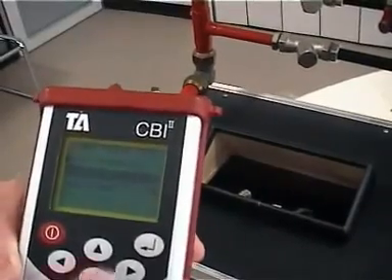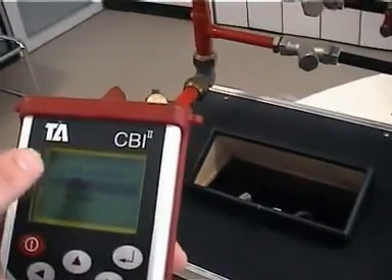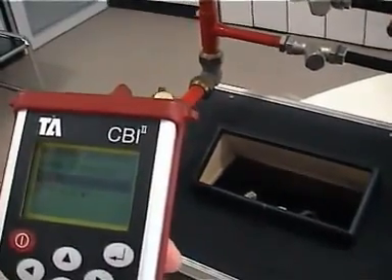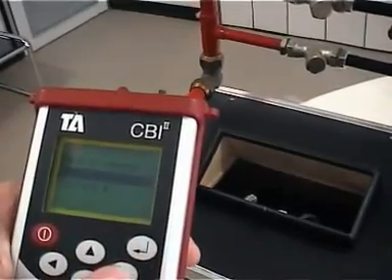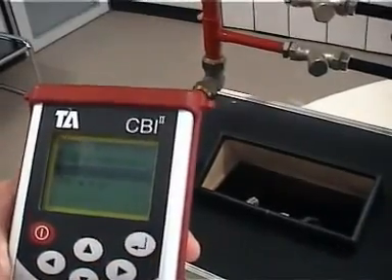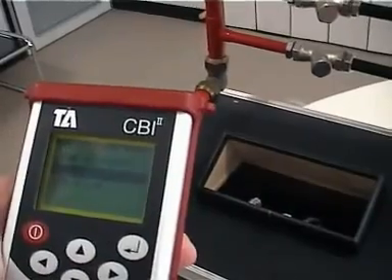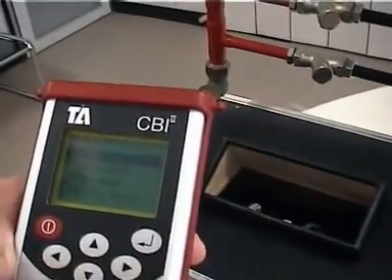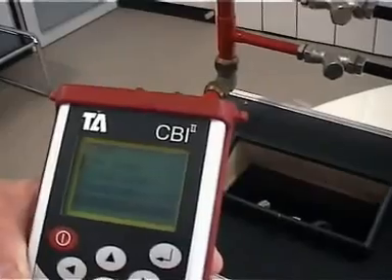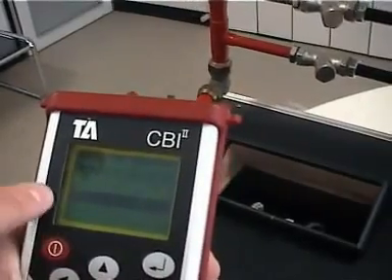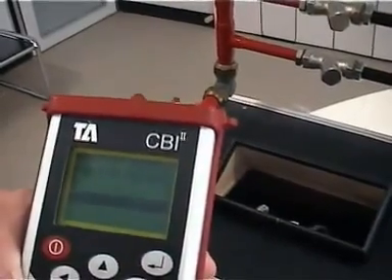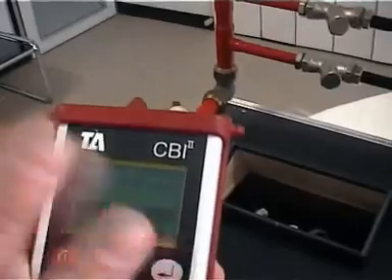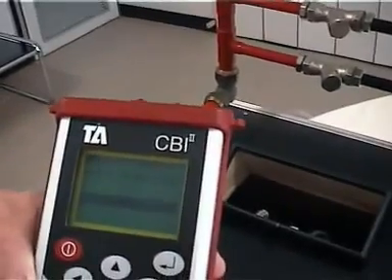We check to see whether we've got the partner valve on, and it's telling us that we're not going to measure the partner valve today. If we wanted to measure the partner valve, move onto yes. If we wanted to change our minimum pressure drop, we come in here, and we change this from 1 to 3 kPa, whatever the minimum pressure drop that we require on the system.